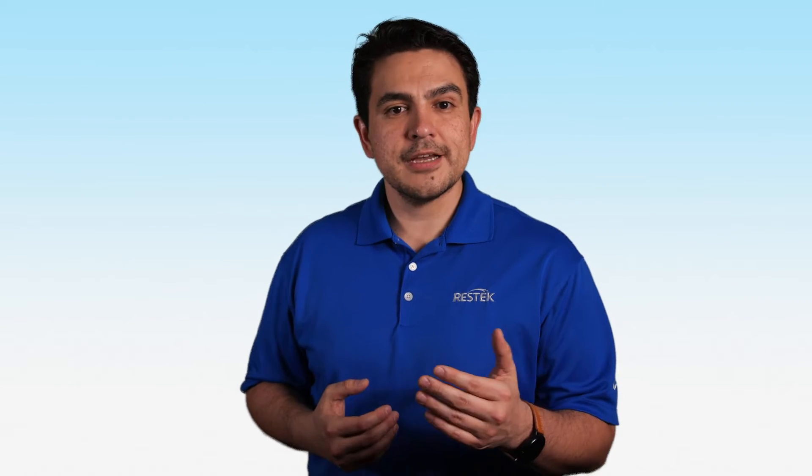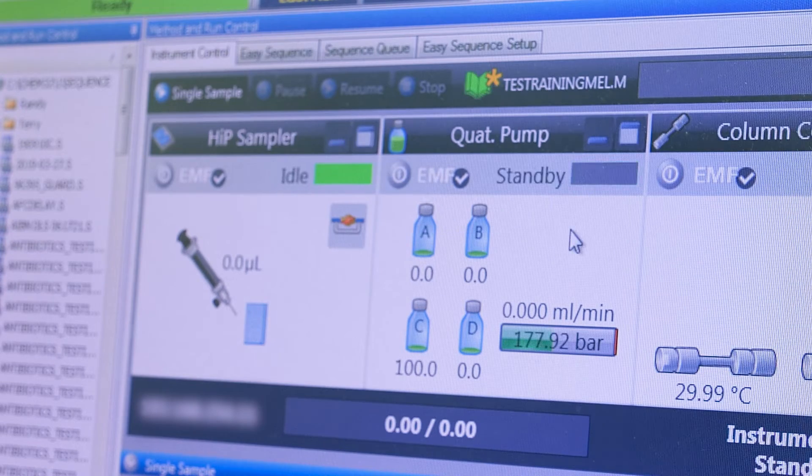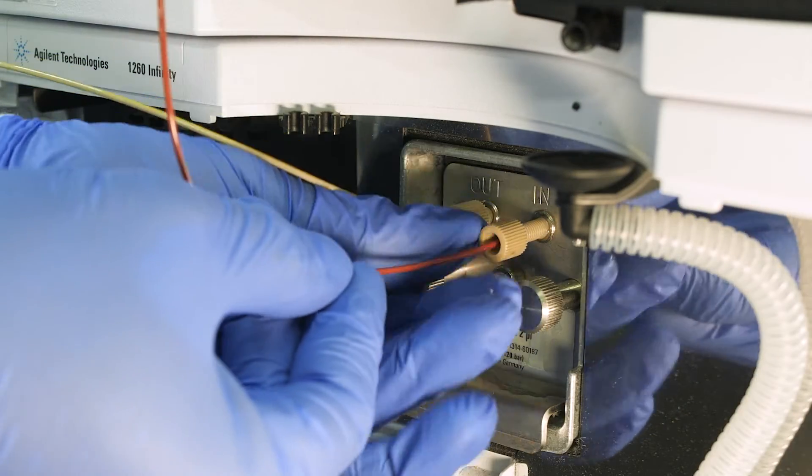One of the most common causes is cell leakage. Cell leakage can occur when there is a leak in the tube fitting that connects the column to the cell. We recommend that you stop the flow, push the tubing into the connection firmly, and retighten it.